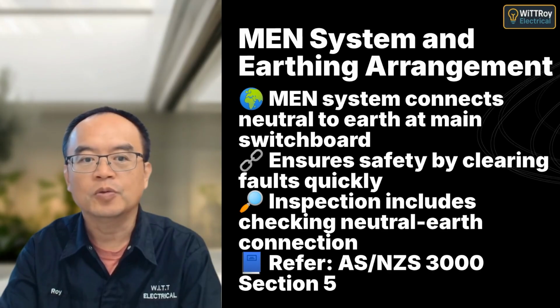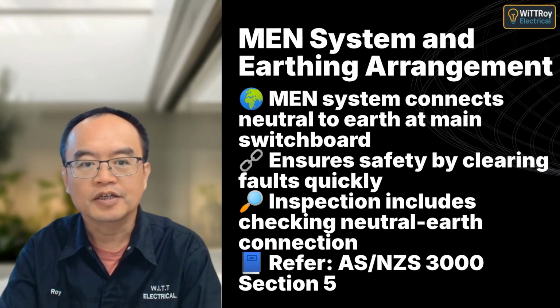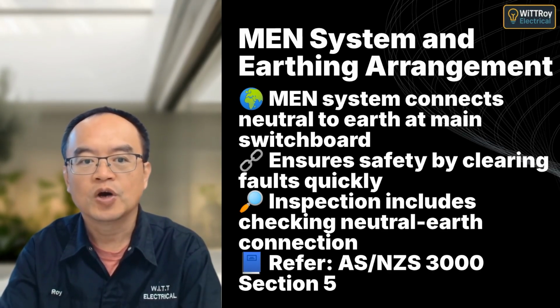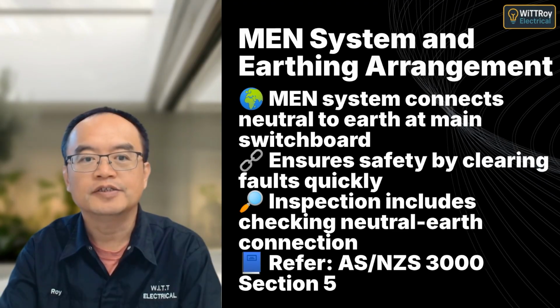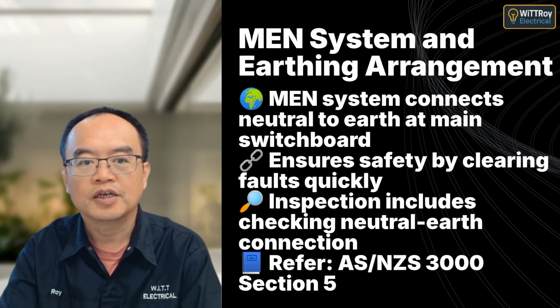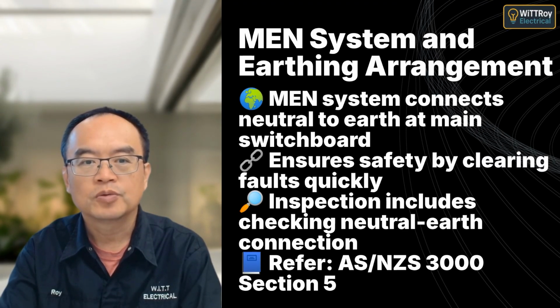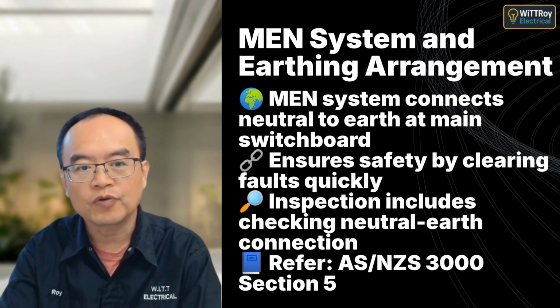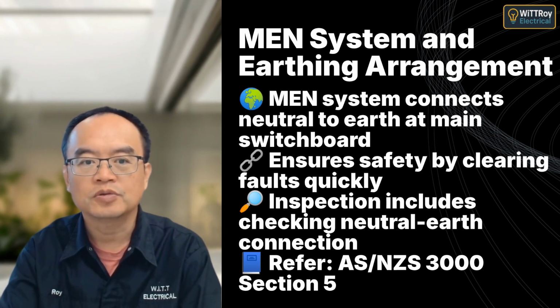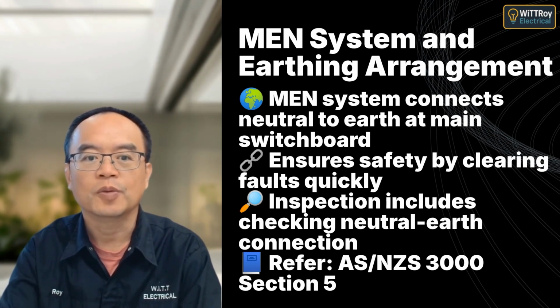The MEN, Multiple Earthed Neutral System, is the standard earthing system in New Zealand. According to Section 5 of AS-NZS 3000, the neutral conductor must be earthed at the main switchboard. This helps ensure that fault currents return to the supply source and protective devices operate correctly.